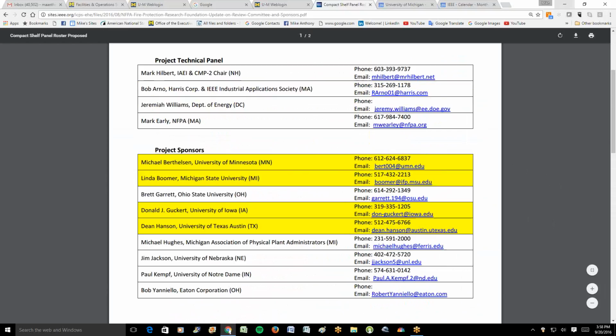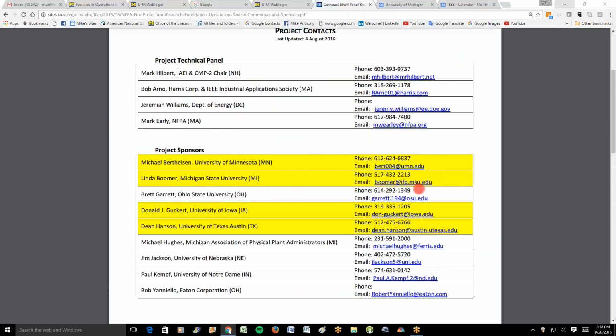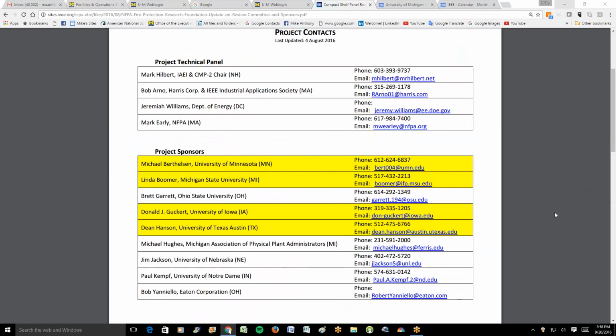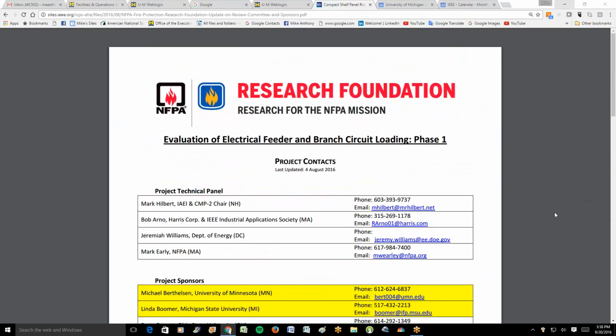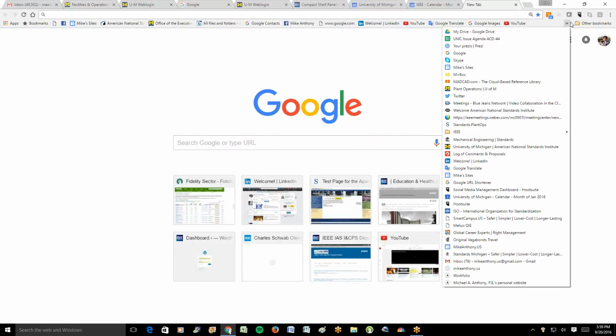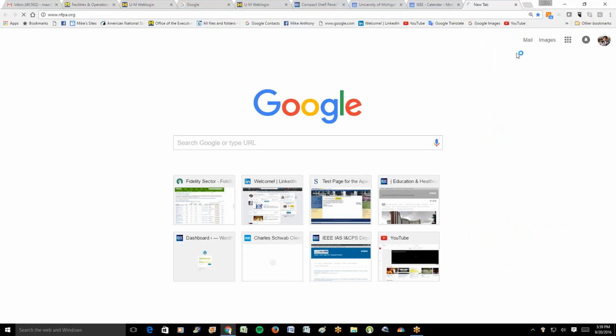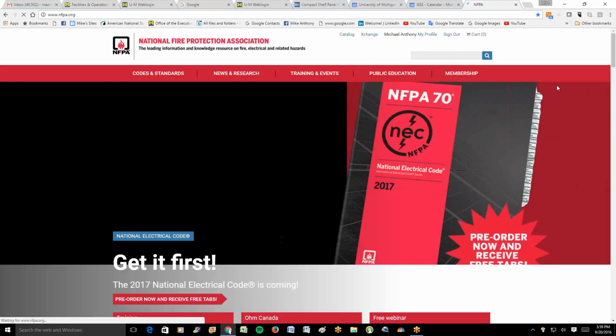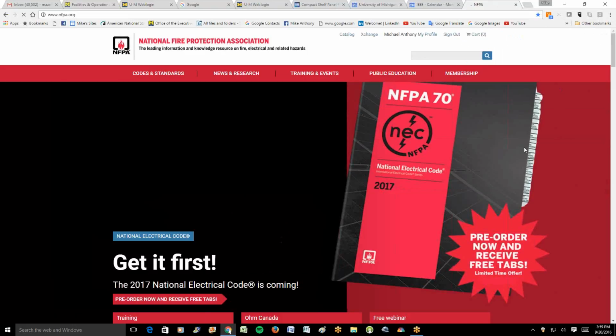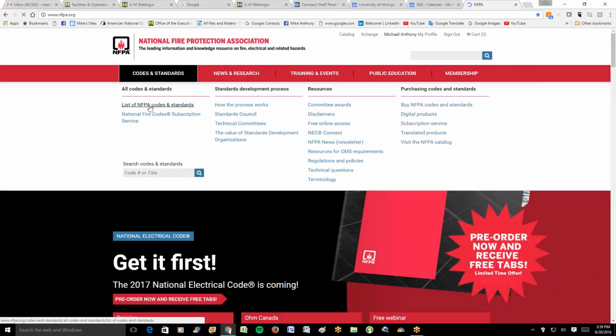But anyway, I won't keep you unless you have any questions, but I have a lot of problems on how to set up a good plan, because if we just evaluate feeders, we're not going to see individual loads. Actually, even just evaluating individual panels supplying branch circuits, usually panels are fed more than one type of load. So for example, how are we going to know what the lighting load is? How are we going to know what the receptacle load is just by evaluating feeder data? And that's what the NEC is doing. I mean, it's specifying the specific loads for lighting, receptacles, and the various main categories of loads in a system.